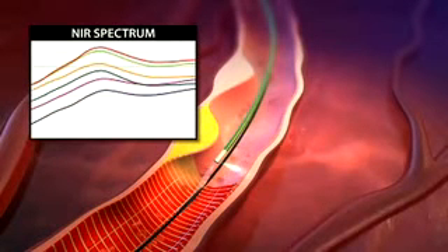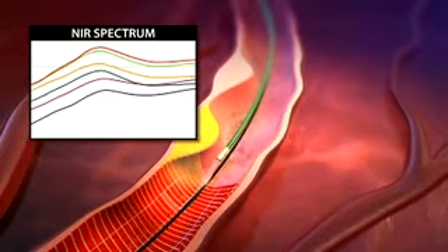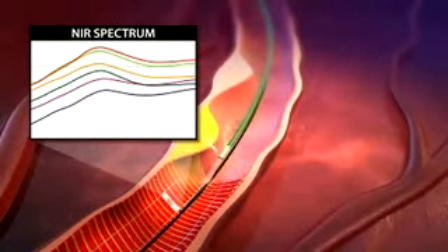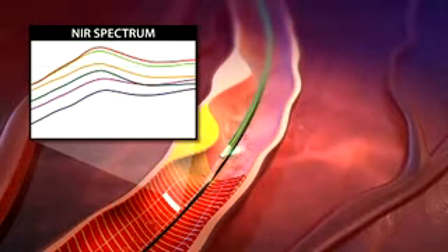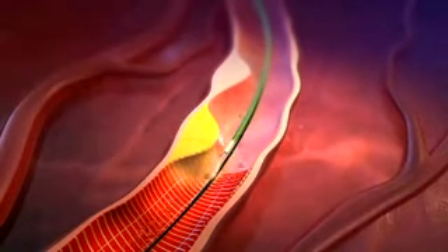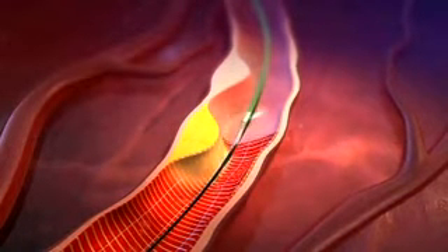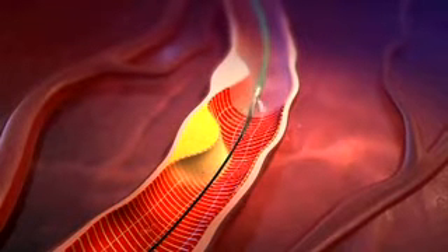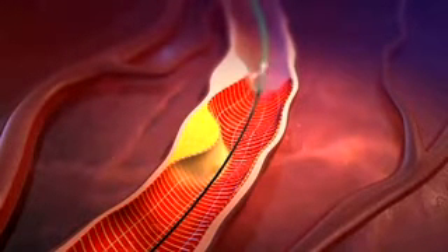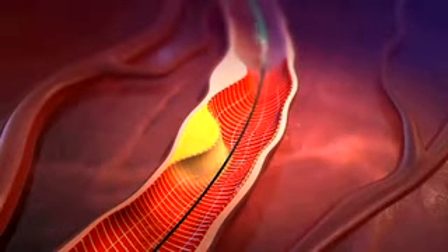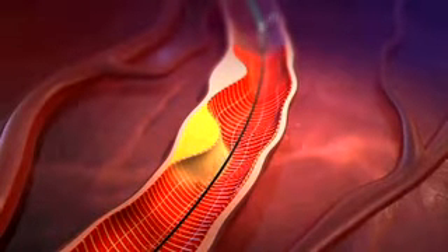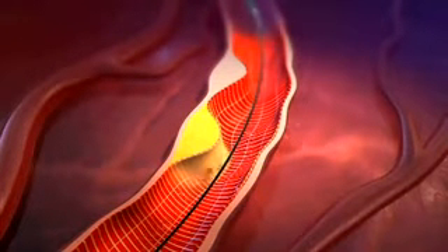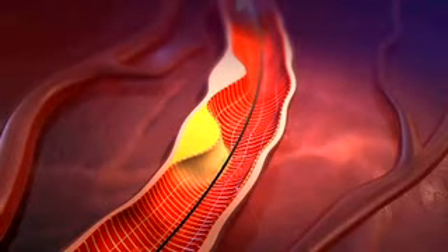This generates a near-infrared spectrum. Each spectrum provides data on the chemical content of a single small area of vessel wall. 40 spectra are acquired per second as the catheter scans the entire vessel. The spectra are analyzed using an algorithm validated in autopsy specimens that indicates the chemical composition of the plaque.